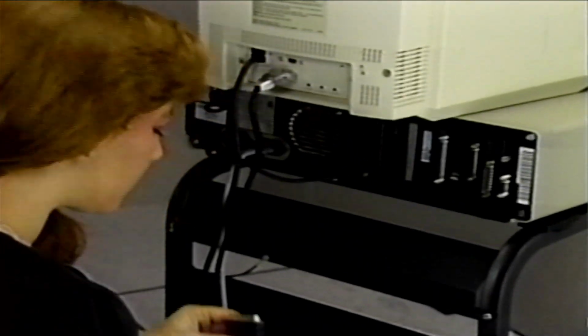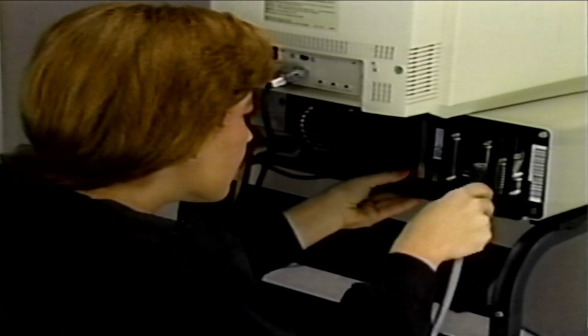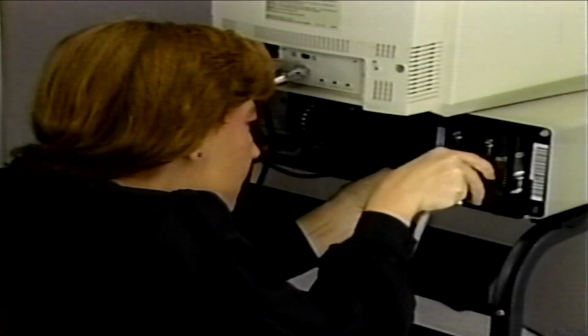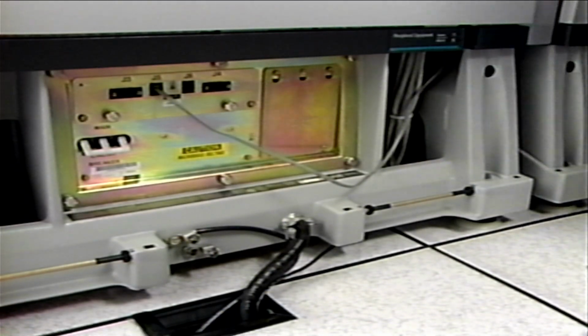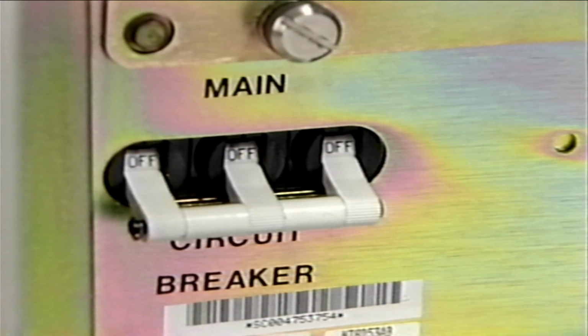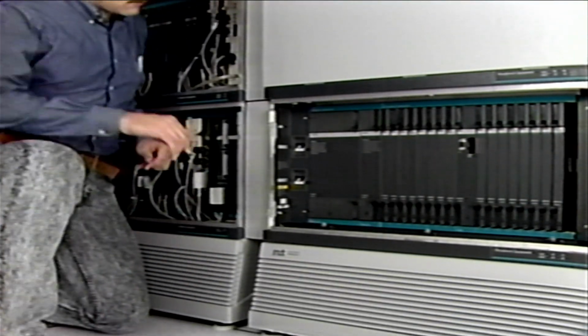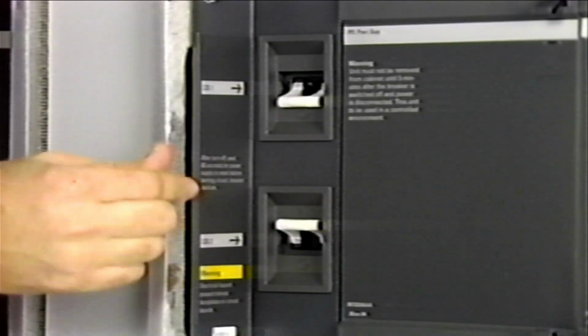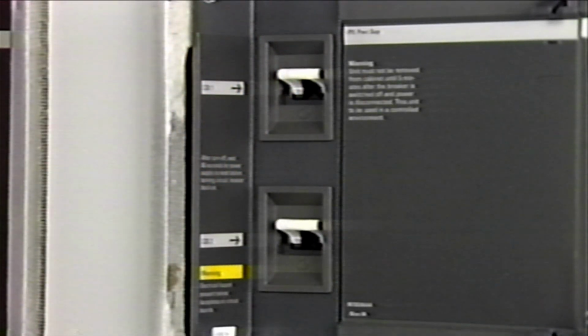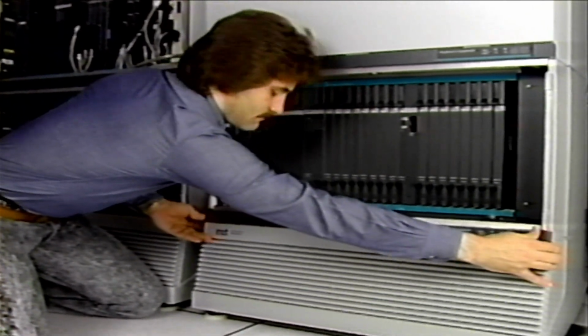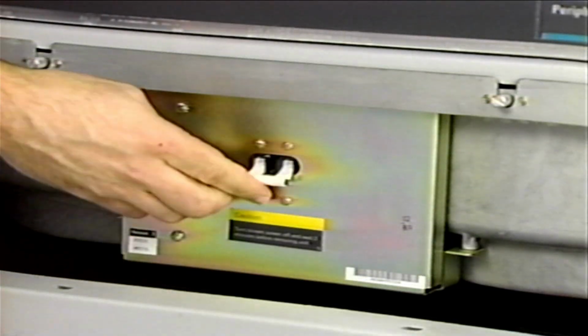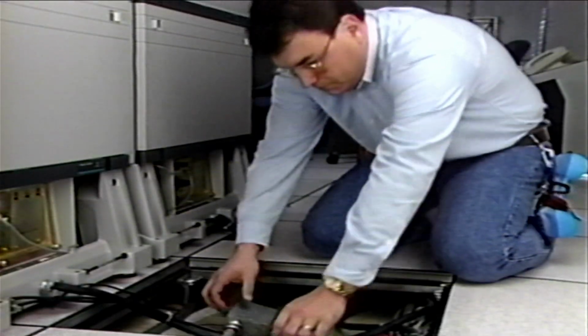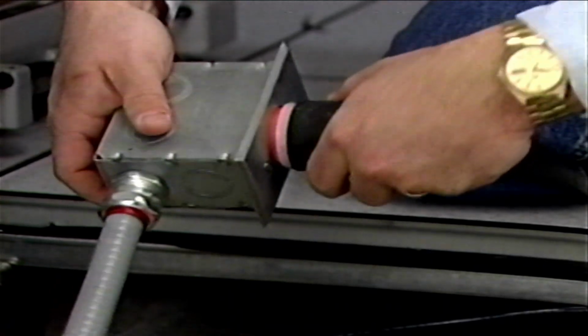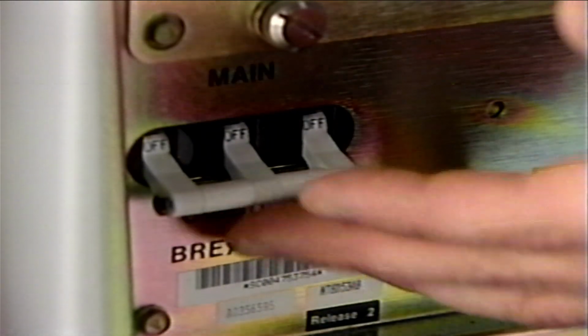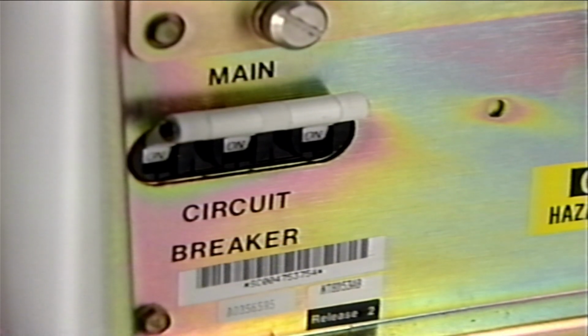Make sure that the system terminal is connected to the Meridian1 so that you can see the initial maintenance messages generated by the system. Now it's time to power up the Meridian1. Check to be sure that the main circuit breaker located at the rear of each pedestal is set to the off position. Next, set the module circuit breakers to the on position. Then, set the circuit breaker for the blowers to the on position. This breaker is located in the front of each pedestal. Next, connect the power cords from each pedestal to the AC power supply outlet. Finally, reset all main circuit breakers to the on position.